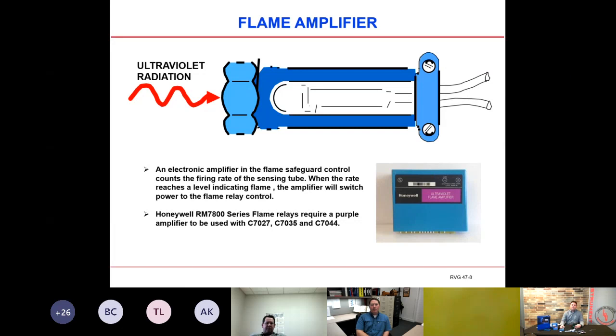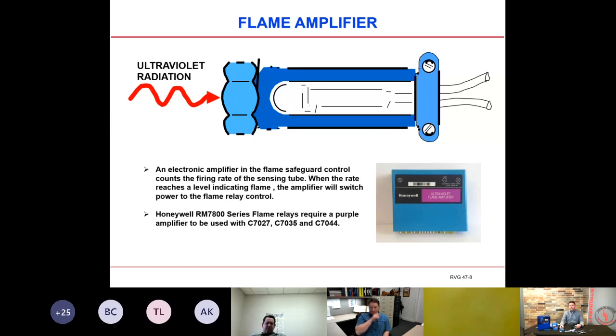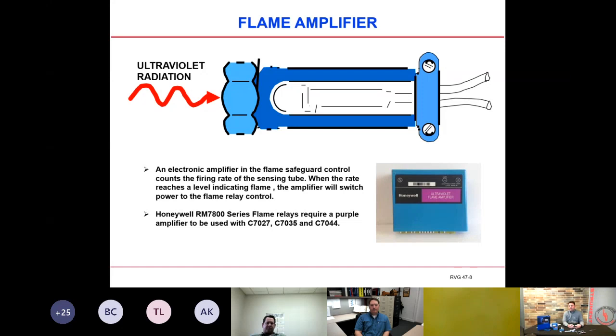Make sure you keep the UV window clean from debris and oil. If you get debris or moisture buildup on the top of the tube, you'll see very low flame signal strength, so preventive maintenance is important. A good approach is to mount the C7027 or UV detector at an angle pointing down toward the burner so any debris that collects in the pipe falls out into the burner chamber. Another option is to add a purge air connection via an NPT fitting between the UV tube and the burner chamber to keep debris away from the lens.